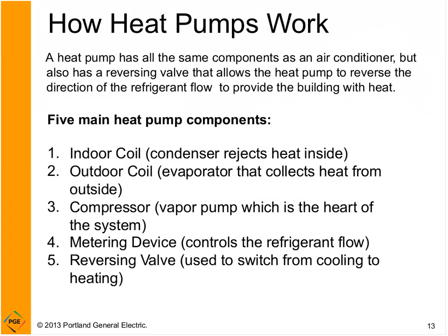A little more on how heat pumps work. Basically, a heat pump has all the same components as an air conditioner, but it also has a reversing valve that allows the heat pump to reverse direction of refrigerant flow and provide the building with heat. So they're very, very similar to an air conditioner. And there's really five main components to a heat pump.